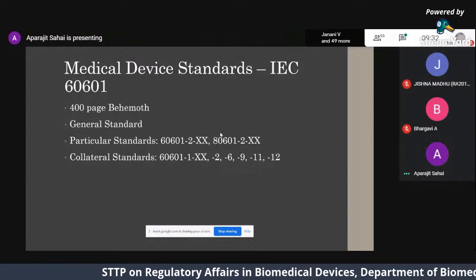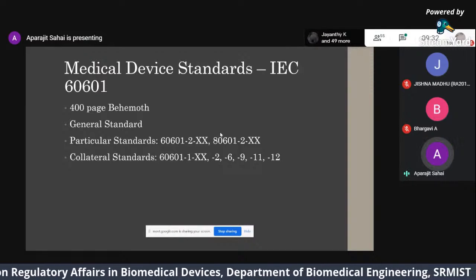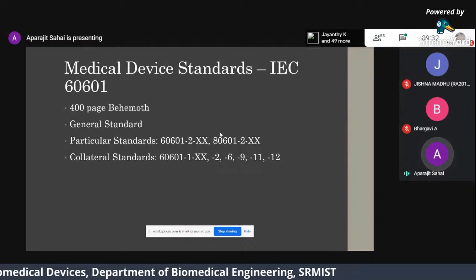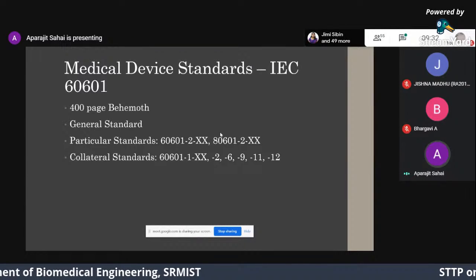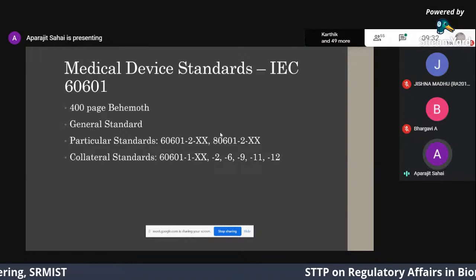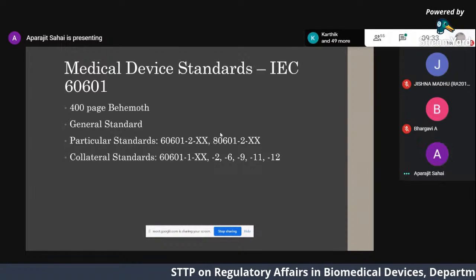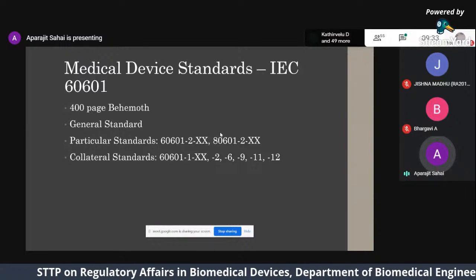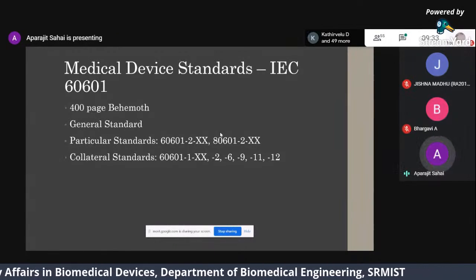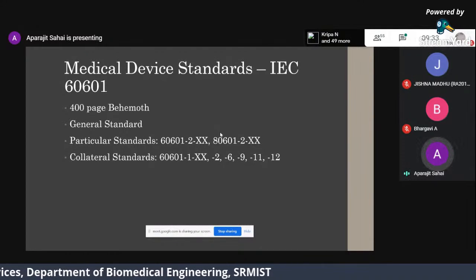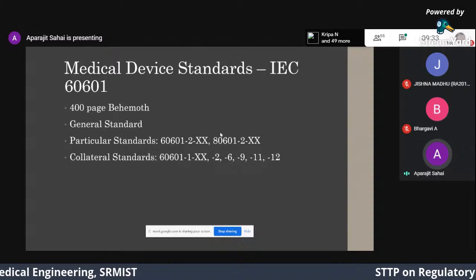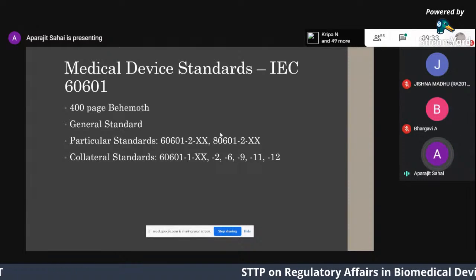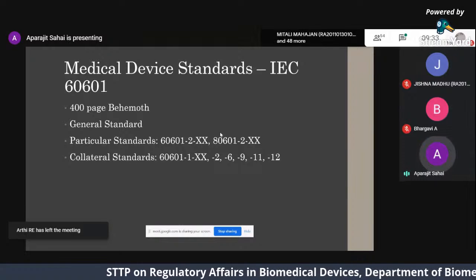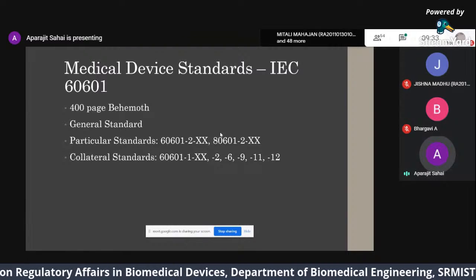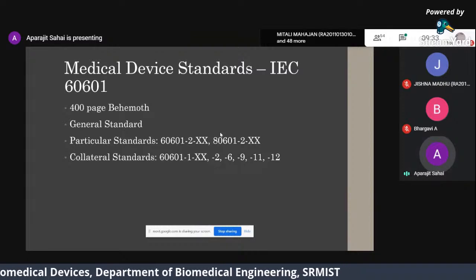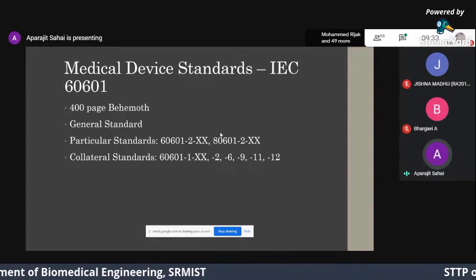And then you have collateral standards, which are also general. For example, a very important collateral standard for electronic and electrical medical devices is EMC, 60601-1-2. Sorry, 60601-1-2. That's the EMC standard, and it lays out requirements for how your device should behave in an electromagnetic field, basically. So if you're putting your electronic or electrical medical device next to other medical devices, that device can interfere. The electromagnetic energy that it produces can interfere with other devices. The electromagnetic energy from those devices can interfere with your device.